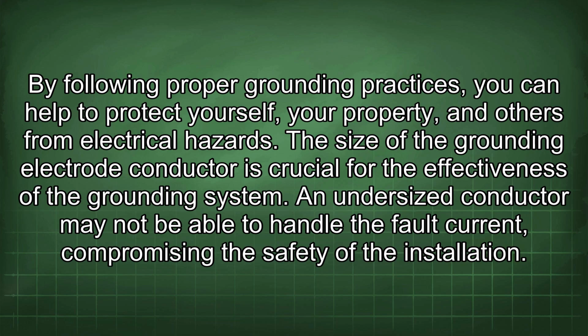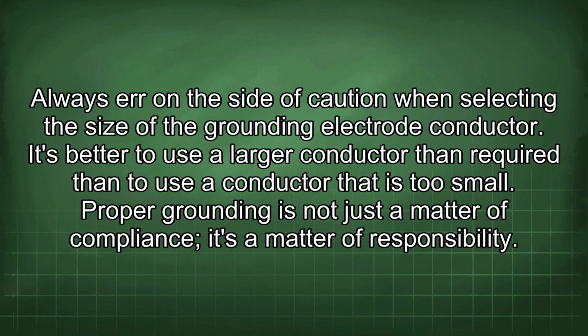The size of the grounding electrode conductor is crucial for the effectiveness of the grounding system. An undersized conductor may not be able to handle the fault current, compromising the safety of the installation. Always err on the side of caution when selecting the size of the grounding electrode conductor. It's better to use a larger conductor than required than to use a conductor that is too small.